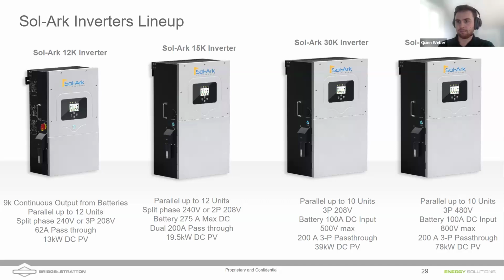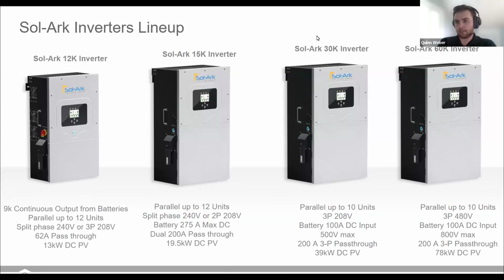The 15 kilowatt is similar. Think of it as a 200 amp transfer switch that you can plug solar and batteries into. It's a transfer switch that can pass a full 200 amps for whole home backup. It can manage batteries and manage an AC coupled source, like if you have existing solar and want to add batteries or a generator, the Sol-Ark can manage that flow between multiple sources of power.